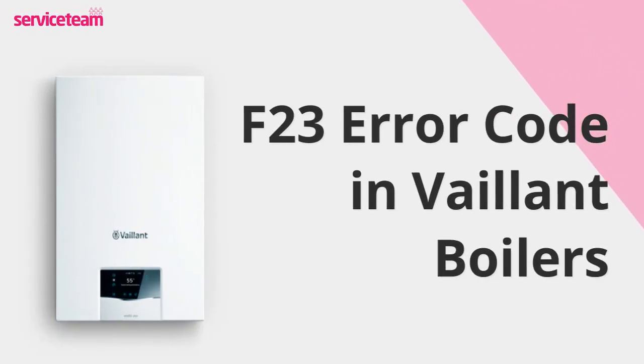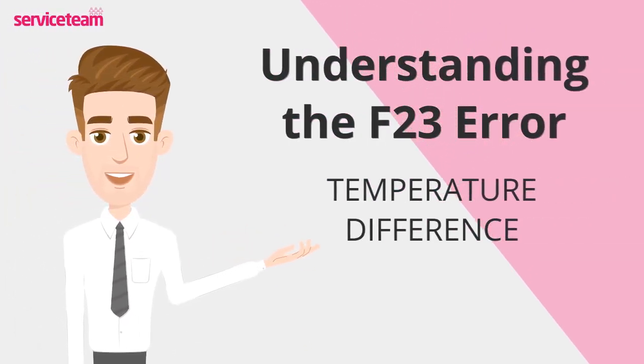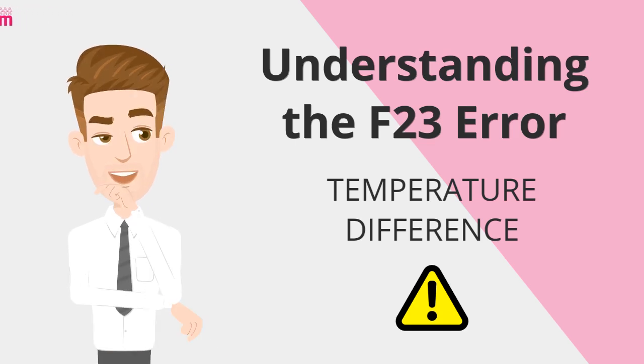Let's figure out how to resolve the F23 error code on the Vaillant boiler. The F23 error code on a Vaillant boiler indicates a temperature difference of over 35 degrees Celsius between the flow and return pipes. This safety feature shuts down the boiler and prevents overheating or potential damage, signaling that something is wrong with your heating system.